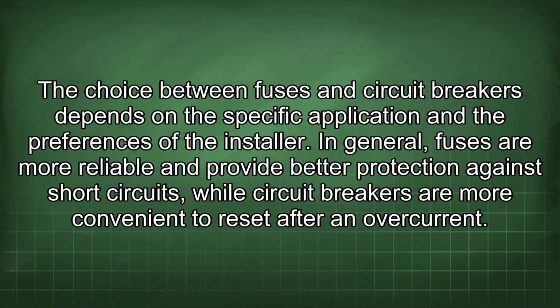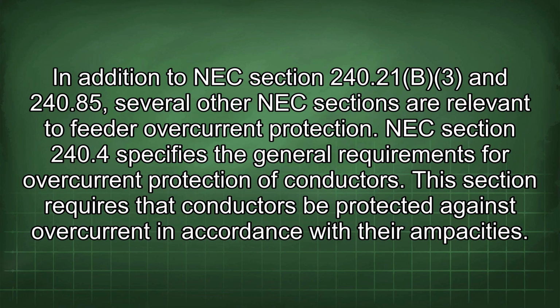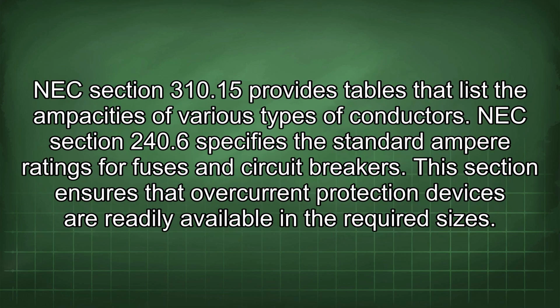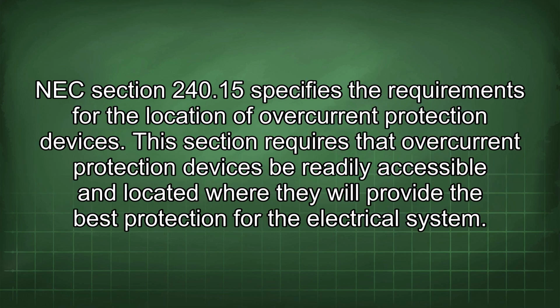In addition to NEC Section 240.21b3 and 240.85, several other NEC sections are relevant to feeder overcurrent protection. NEC Section 240.4 specifies the general requirements for overcurrent protection of conductors. This section requires that conductors be protected against overcurrent in accordance with their ampacities. NEC Section 310.15 provides tables that list the ampacities of various types of conductors. NEC Section 240.6 specifies the standard ampere ratings for fuses and circuit breakers. This section ensures that overcurrent protection devices are readily available in the required sizes. NEC Section 240.15 specifies the requirements for the location of overcurrent protection devices.